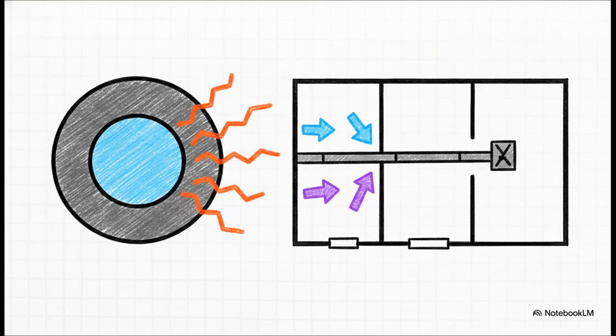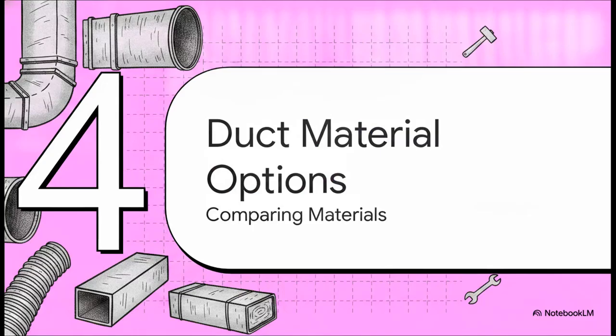But you see, sealing is really only the first barrier. We take those incredibly tight seals and combine them with high-grade R6 or R8 insulation. This thick thermal barrier completely insulates the cold air inside the duct from the extreme heat of your attic, which is exactly what stops that damaging condensation we talked about earlier. Furthermore, for our larger homes, we implement smart zoning systems. This allows for incredibly efficient airflow control, so you're directing cooling only where it's needed, exactly when it's needed. Which leads us to Section 4, comparing duct material options.